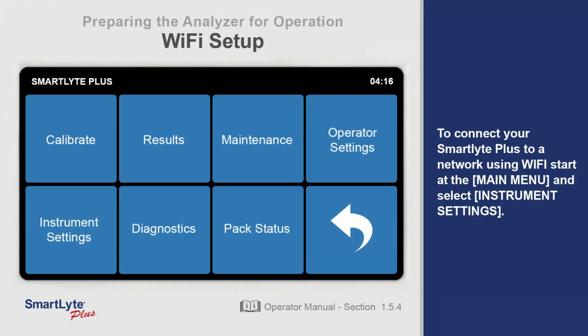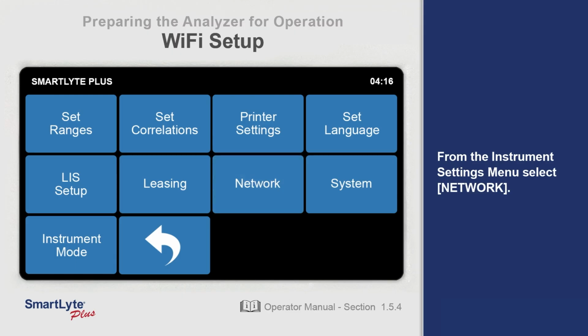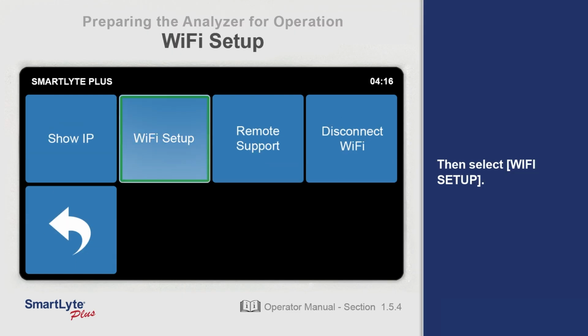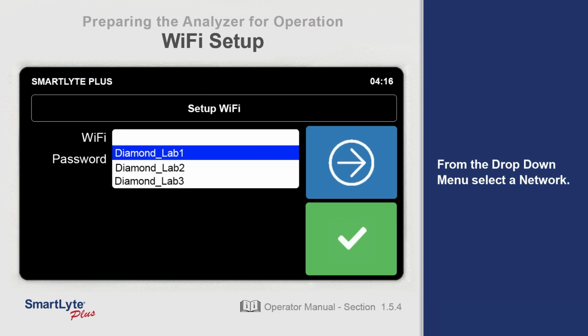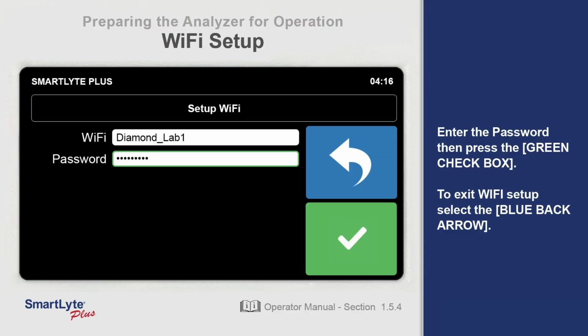To connect your SmartLyte Plus to a network using Wi-Fi, start at the main menu and select Instrument Settings. From the Instrument Settings menu, select Network. Then select Wi-Fi Setup. From the drop-down menu, select the network that you would like to connect to. Enter the password, then press the green checkbox. To exit Wi-Fi Setup, select the blue back arrow.